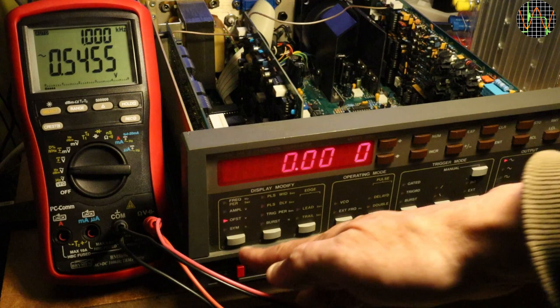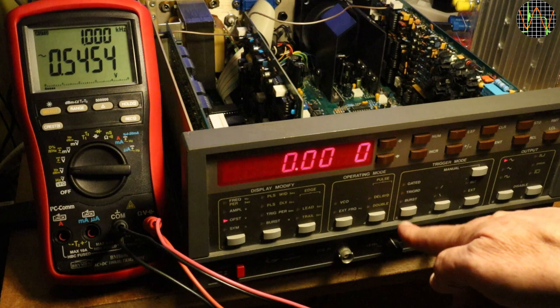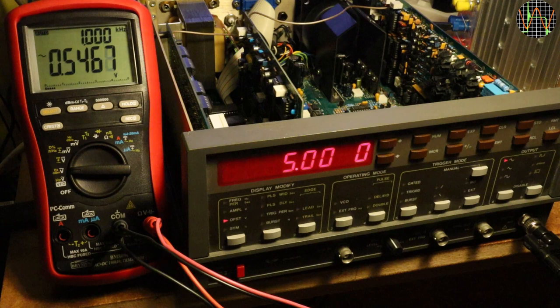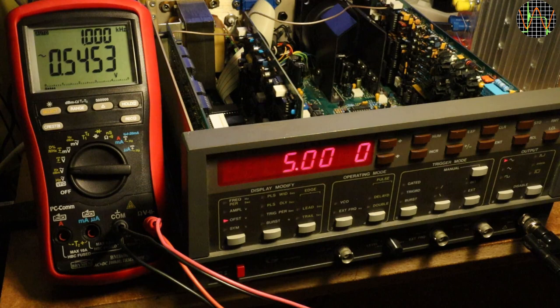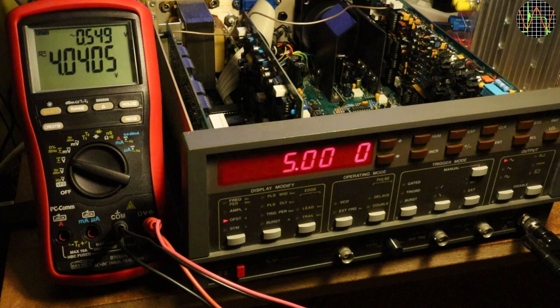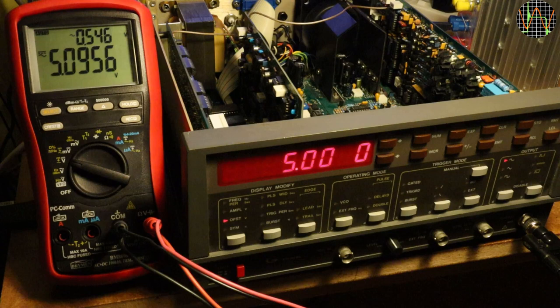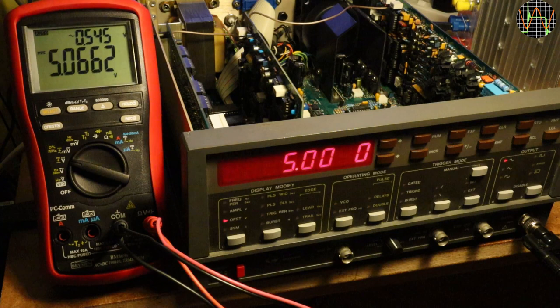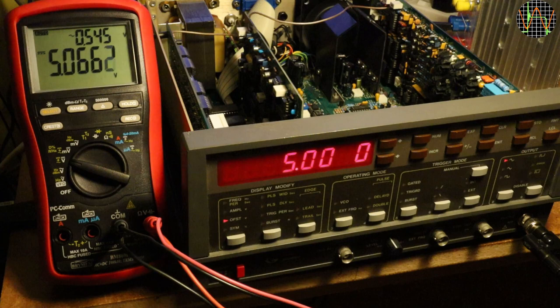Let's look at offset instead. This generator with all buttons the same colour and in no logical order is a usability nightmare. One day I swear I put different coloured dots on num, exp and ent. Anyway, I finally have a plus 5V offset. I have to deviate from the manual because the BM869S in AC mode does not care about DC offsets. I could use AC plus DC mode but I am not sure if the meter and procedure was doing that either. So I decided to simply use the BM869S showing AC and DC components separately which you see now. It looks as if at 5.06V the offset is a little too high. Anyway, there is no point continuing testing other offset values until that is fixed.